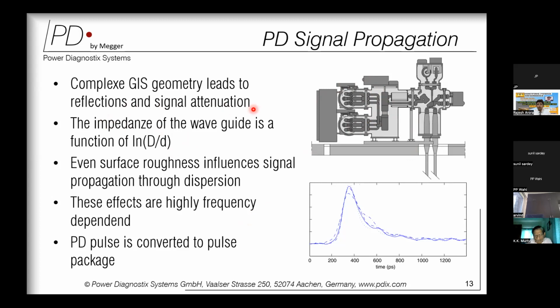These different diameters of the GIS basically act as a waveguide and provide a variable impedance to the emitted signal. As we know, whenever a signal is transmitted through any medium, it encounters a change in impedance and reflects a certain amount of the waveform. So each change in diameter of this GIS enclosure or waveguide will reflect some signal back, and hence there is back and forth reflection of the partial discharge signal.